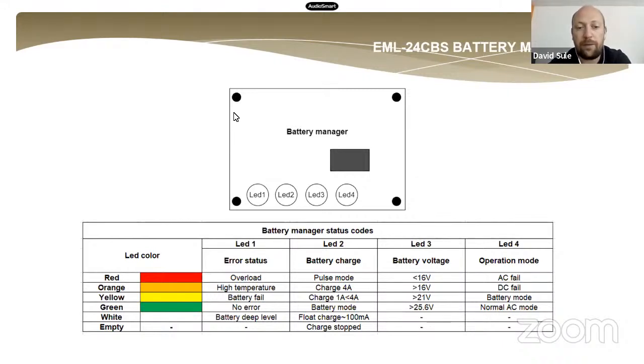It can show temperature errors, battery fail events, and battery deep level. It can show the battery charging, whether it is in pulse mode or 4 amp charge mode, or whether the panel is in battery mode, so we don't have AC 230 in the system. So a lot of information can be read from the battery manager too.